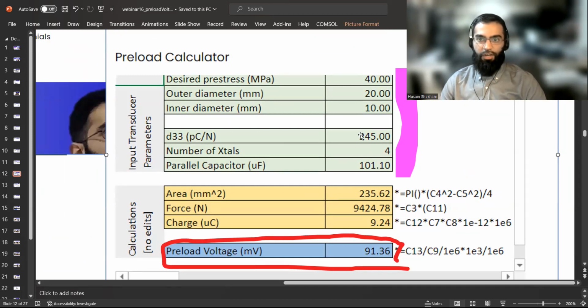It's not too hard - you type in your D33, you can use the assumed value from your manufacturer, the number of crystals you have, which will probably be 2 or 4 for a power transducer, and the parallel capacitor you're using. Then all of these things will be calculated for you, but the thing you want is here: 91.36 millivolts that you need to shoot for.